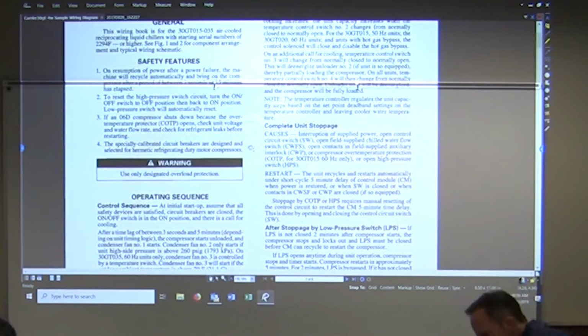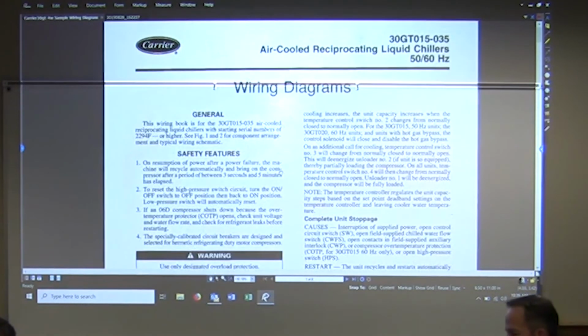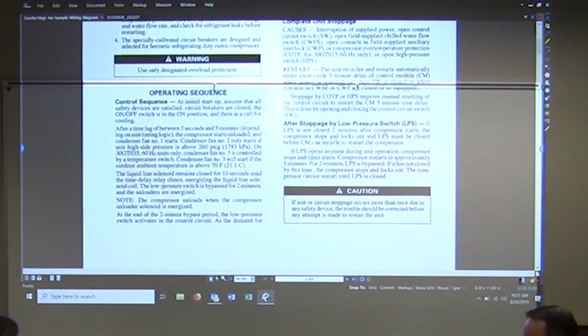Okay. All right, let's switch over to our other piece, which is going to be the carrier. So I found this carrier wiring diagram a number of years ago, and I thought it was a pretty medium kind of representation of a wiring diagram you might find out in the field. It's not as hard as some, but it does have a little bit of, hard to read maybe at first. And so I think it's a good one that we work on, look through to try to troubleshoot and figure out how do we wire this, how do we put a meter on it, check things, and come to understand what's going on. So if you're not familiar with how a chiller operation works, this has, much like we just mentioned, an operating sequence.